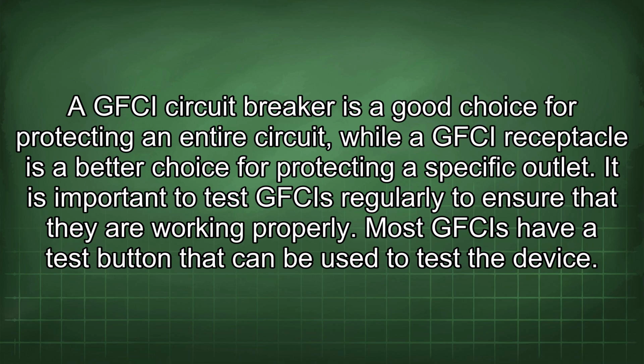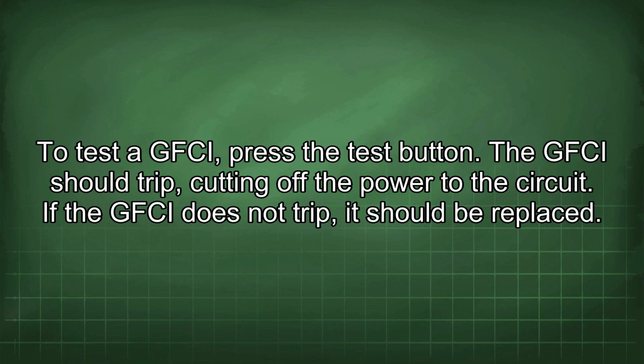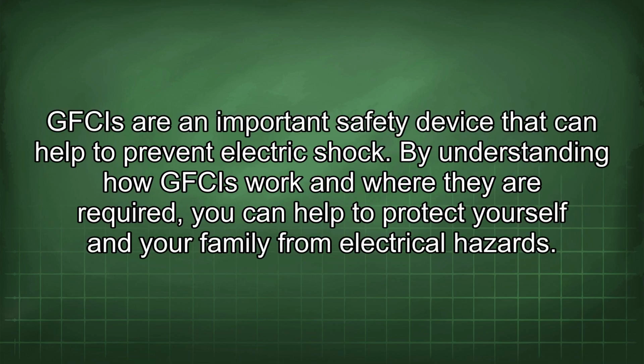It is important to test GFCIs regularly to ensure that they are working properly. Most GFCIs have a test button that can be used to test the device. To test a GFCI, press the test button. The GFCI should trip, cutting off the power to the circuit. If the GFCI does not trip, it should be replaced. GFCIs are an important safety device that can help to prevent electric shock. By understanding how GFCIs work and where they are required, you can help to protect yourself and your family from electrical hazards.